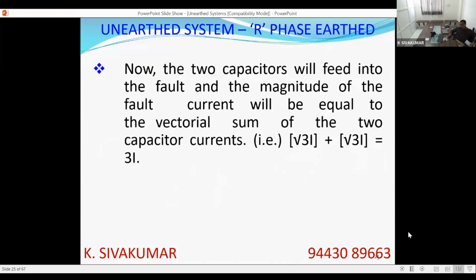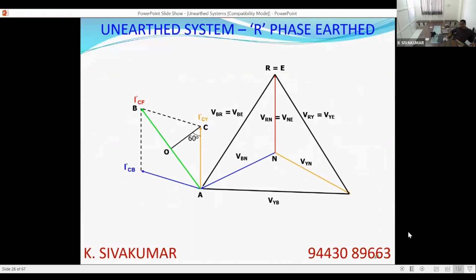Now, the two capacitors will discharge into the fault, will feed into the fault, and the magnitude of the fault current will be equal to the vector sum of the phase currents, that is √3 I and √3 I, which will become 3I. Like this, in this triangle, you can do the trigonometrical equation. The vector AB will be equal to 3I actually.